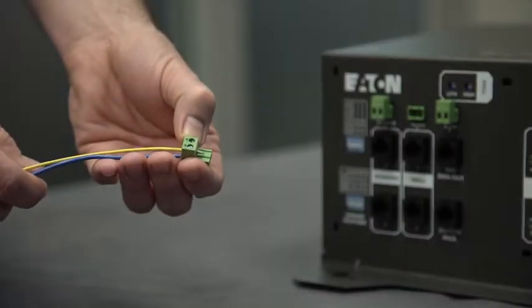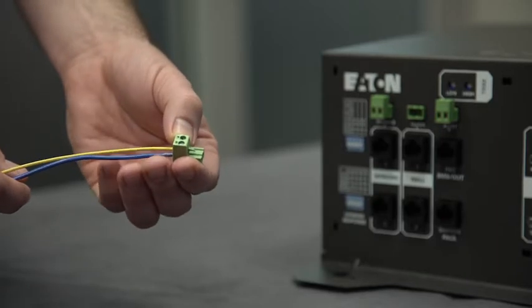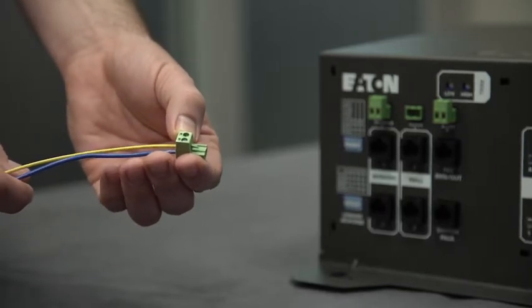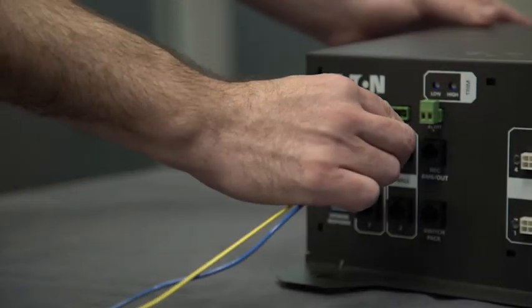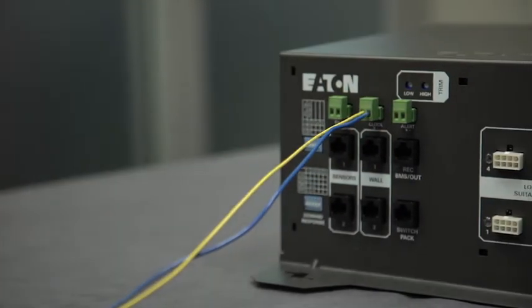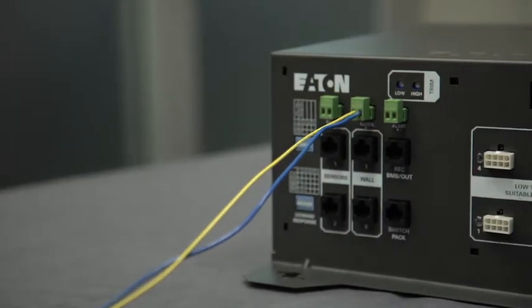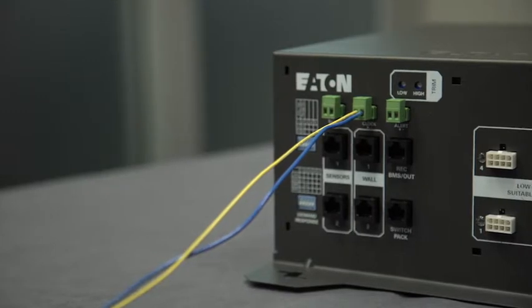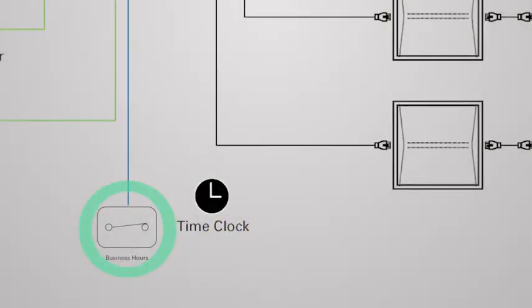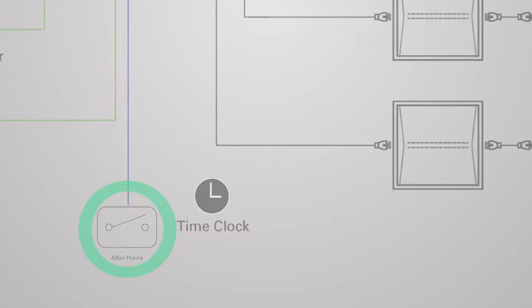To attach the time clock to the system, connect 18 gauge two conductor twisted pair between the time clock's dry contact output and the power module's time clock terminal. This is not a polarity sensitive connection. The external time clock must be programmed so that it closes the contact during business hours and opens the contact after hours.